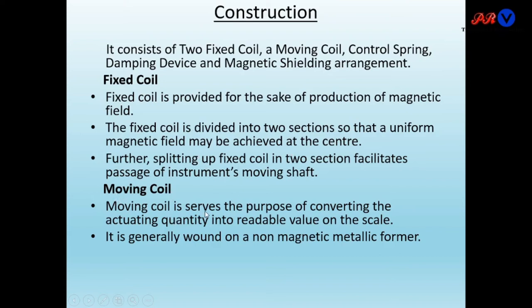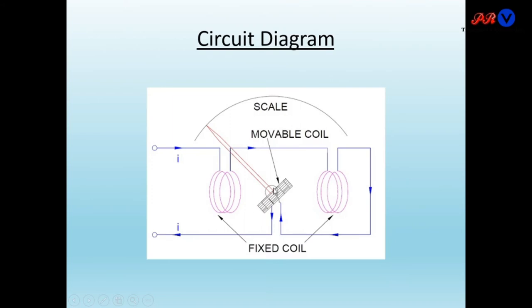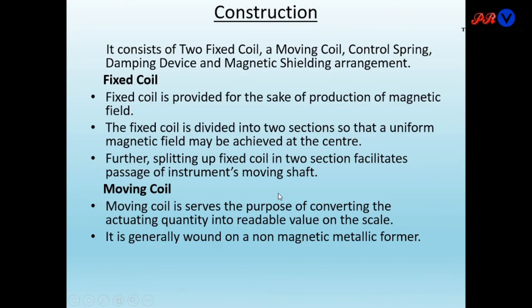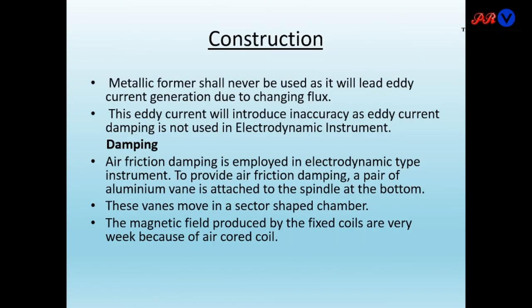The moving coil serves the purpose of converting the actuating quantity into a readable value on the scale — the actuating quantity can be current or voltage. It is generally wound on a non-magnetic metallic former. A metallic former shall never be used as it will lead to eddy current generation due to changing flux.